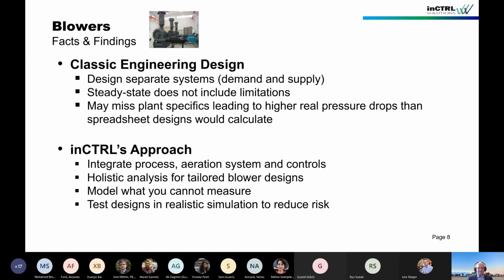And the other thing with this approach is that you can test the designs in a realistic simulation to really reduce risk when you go to commissioning. Because if you model it as realistically as possible, then the controller tuning that you develop in the model is going to be a really good starting place for the tuning in the plant. You'll always have to fine tune, of course, but you'll have a really good starting point.